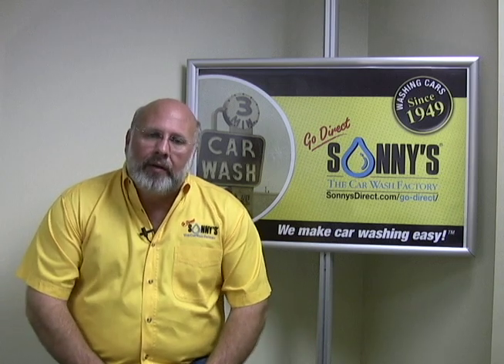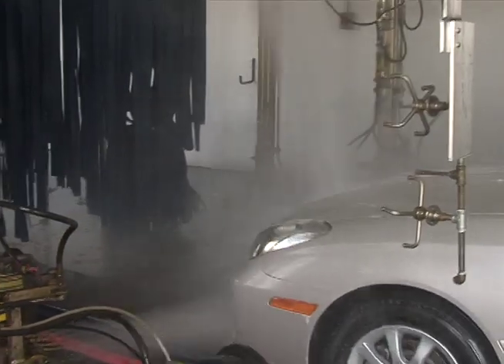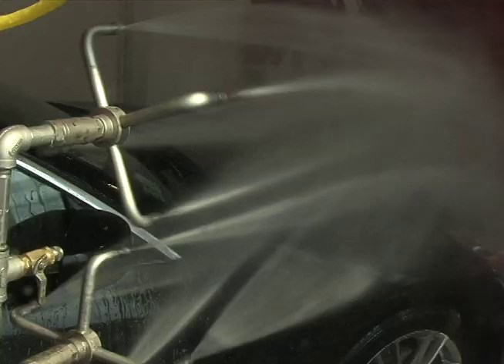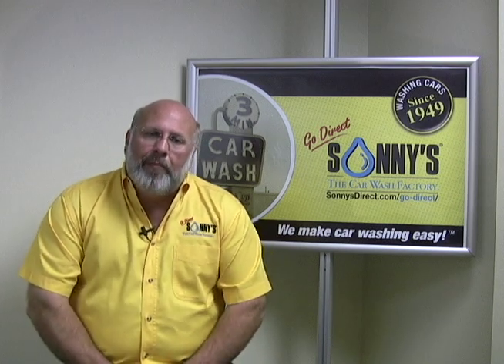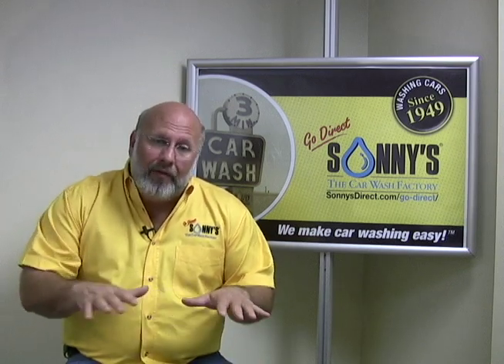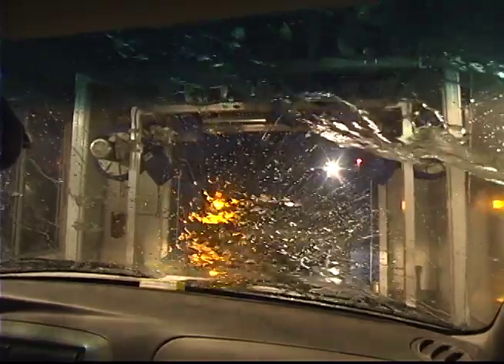The first part is a water repressurization system. We use this to manage the water pressure within the car wash building. If the city believes they're going to give us 60 PSI when they tap into that 8-inch or 10-inch water main in the street and go through the backflow preventer, a lot of times we get that 60 PSI with one valve open, but when we open all those valves, we drop sometimes below 20 or 25 PSI. So we're not asking for more water — we're just asking for what they tell us they'll give us, and we're going to manage that within our own facility. We'll put in a repressurization system driven by a variable frequency drive that'll manage that water pressure. If the water's at 60 PSI, it does nothing — it won't even run. If it drops below that as we start opening valves or it's a busy Saturday, it'll just bring that pressure up and maintain that 60 PSI and the right flow rate within our tunnel walls.